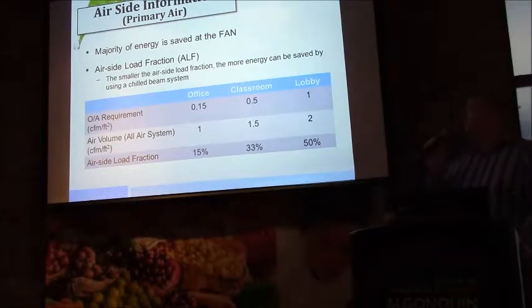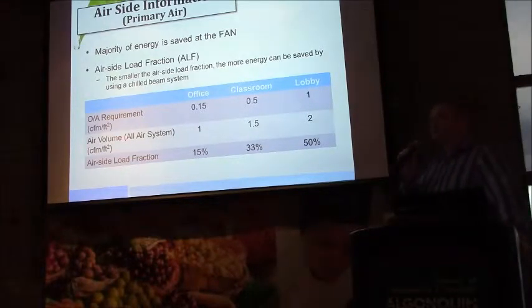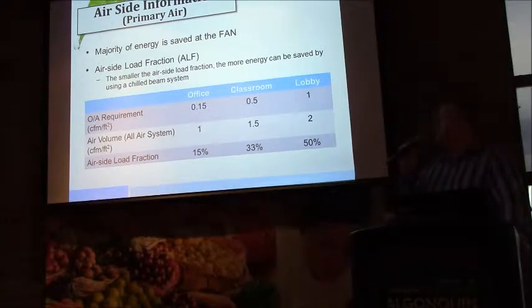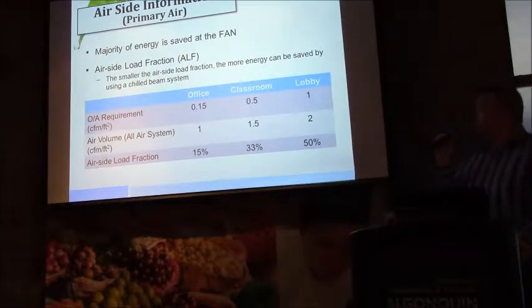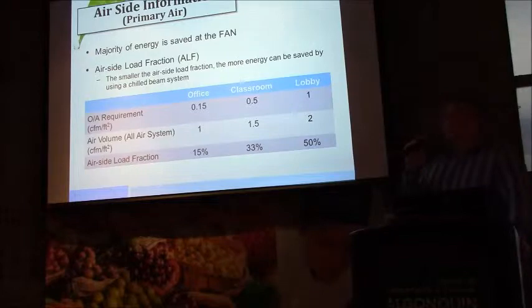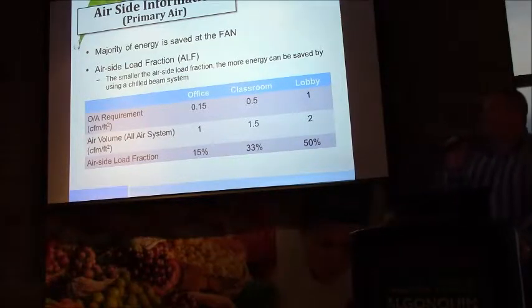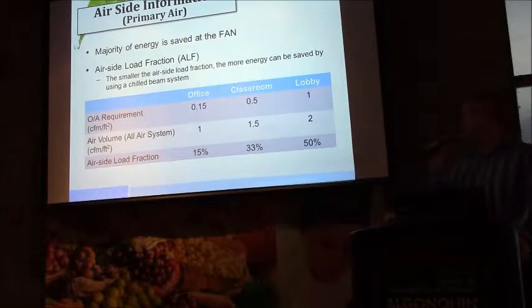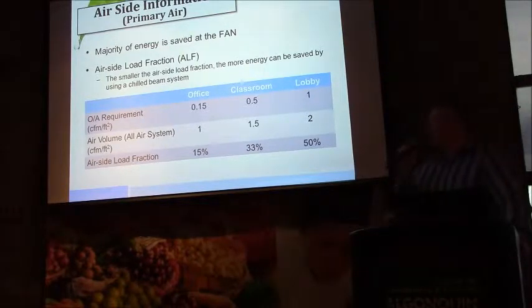And we'll see in some of the zones that offices conceivably could be a very appropriate option or opportunity for an active beam, given that the latent load is modest, because of the occupancy, of course. And the sensible load could be moderate to reasonably high. Classrooms, where our latent loads are becoming more significant or more relevant to the space in terms of vetting the issue as to whether or not a beam is appropriate, all the way up to, say, a lobby, for the conditions that we described earlier, whereby it just might not be the right solution, and that's okay.